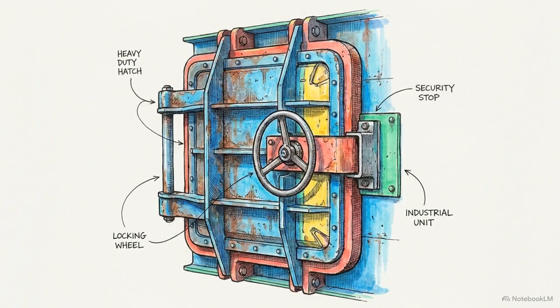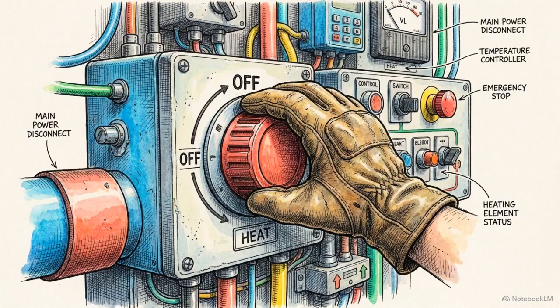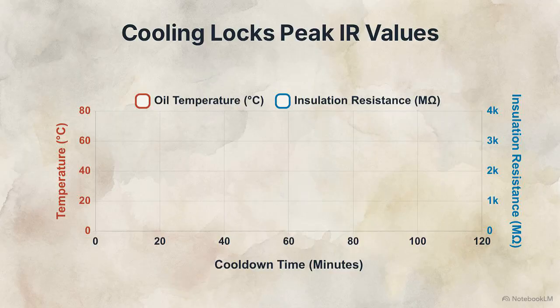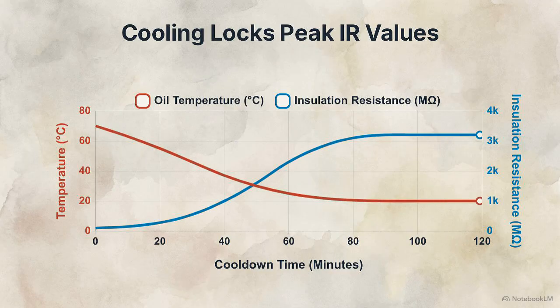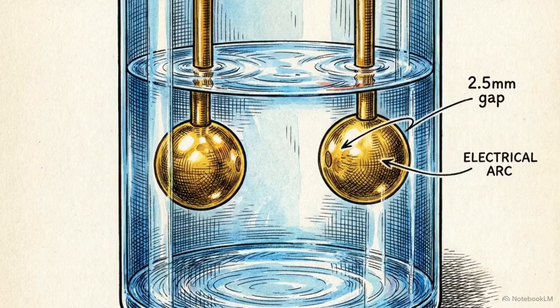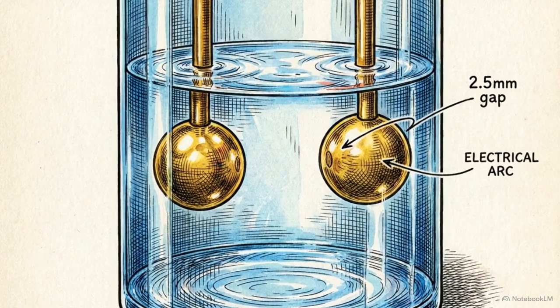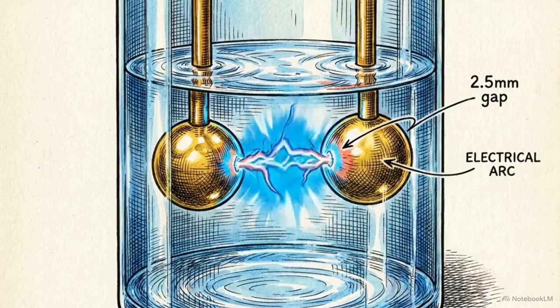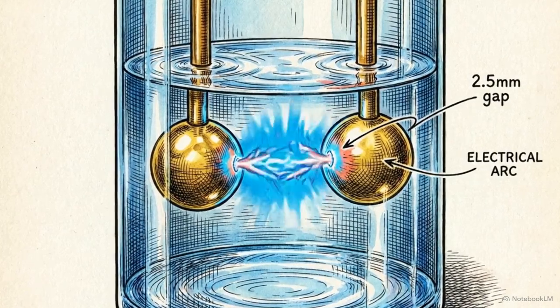Hitting the 60 kilovolt BDV mark and the steady IR plateau confirms the internal environment is dry, concluding the active dehydration phase. Turn off the heaters and allow the transformer to cool completely to ambient temperature. As the oil cools, you will see the IR values naturally peak and lock in their final position. Draw a final ambient oil sample. It must pass a 50 kilovolt dielectric test across a 2.5 millimeter gap.